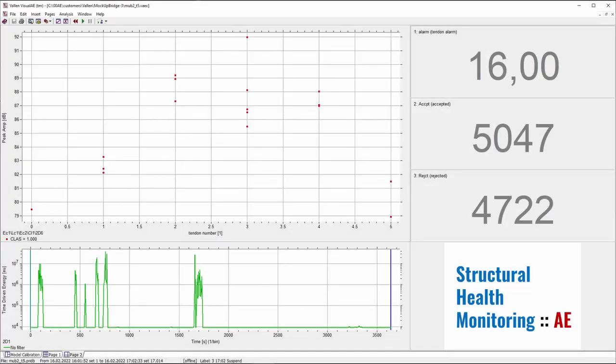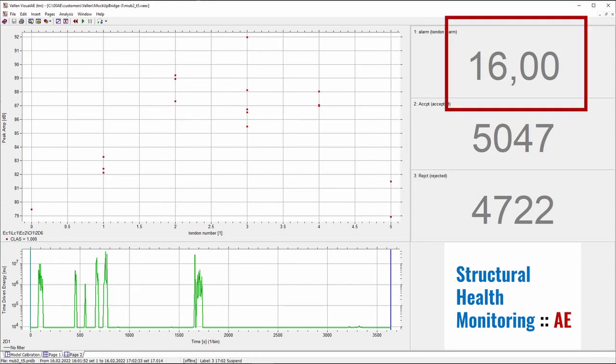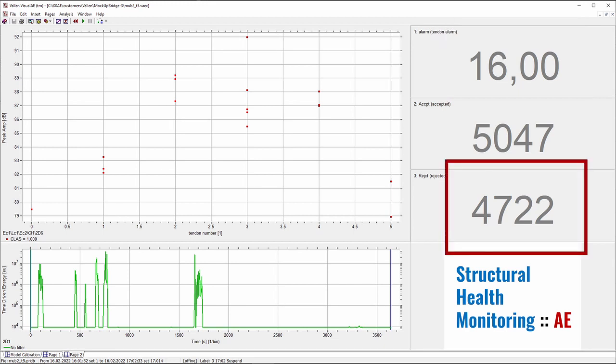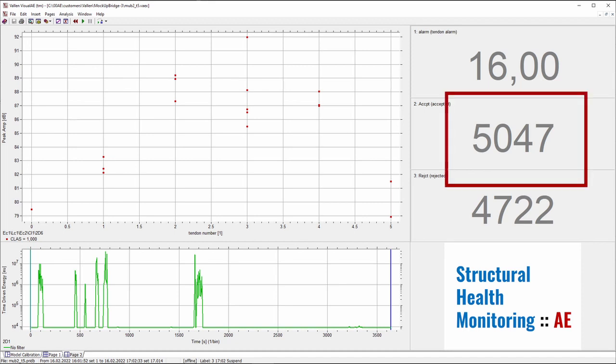The whole analysis setup can be condensed into one simplified page. The simplified setup shows how many signals made the alarm criterion for a wire failure. We also get some statistical information about how much noise has been rejected and how many signals were accepted. This is valuable information for trending.